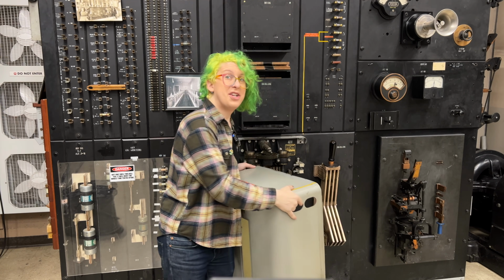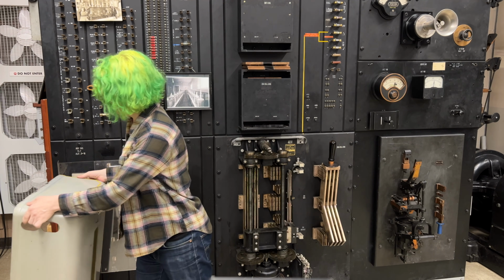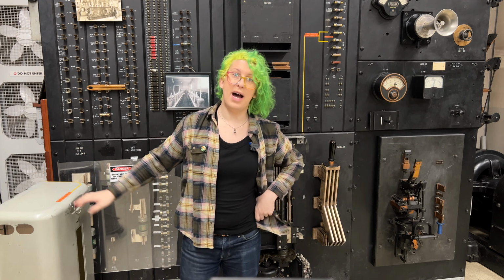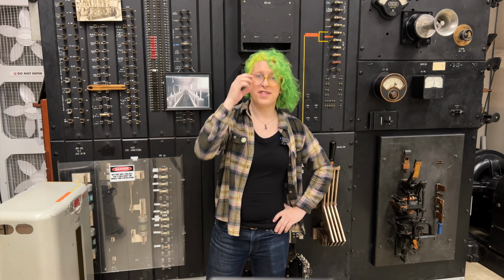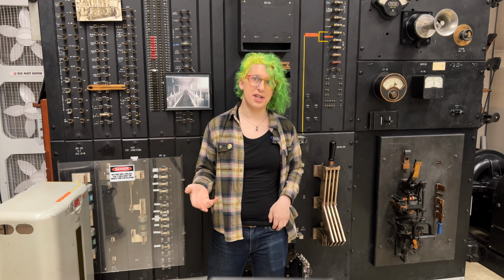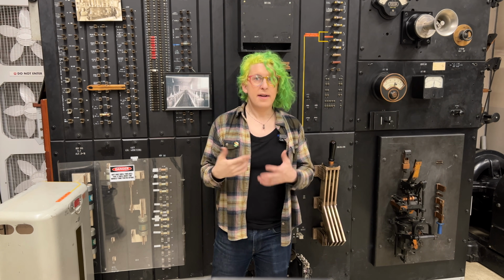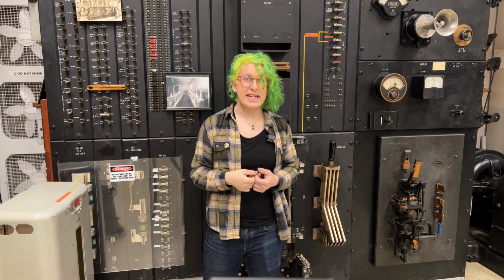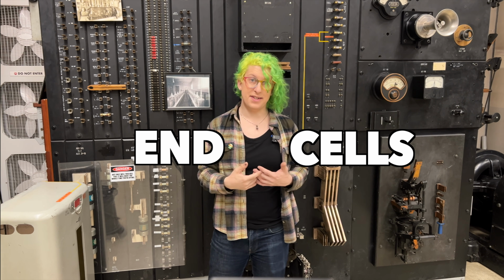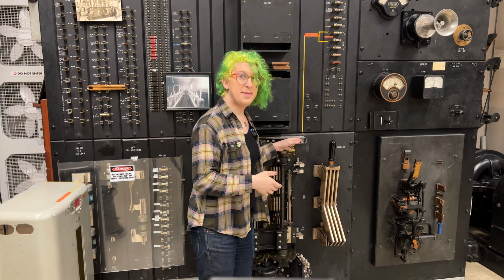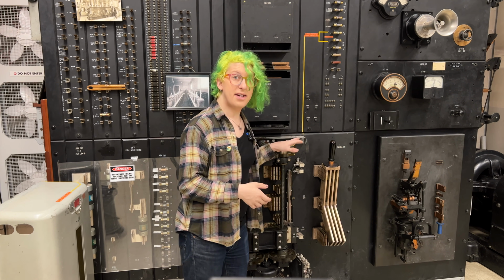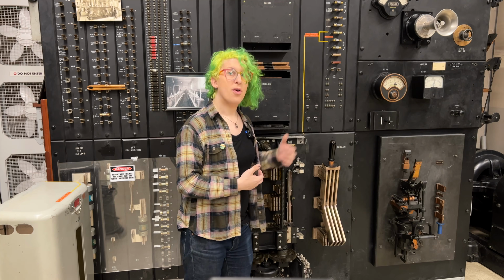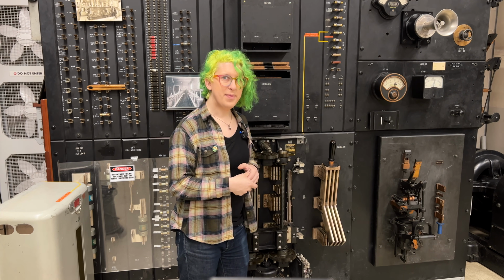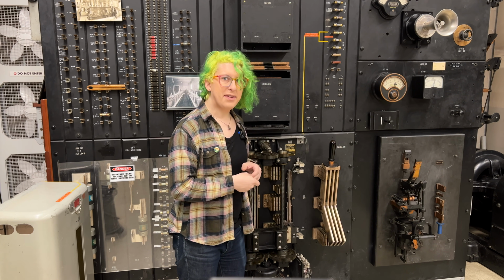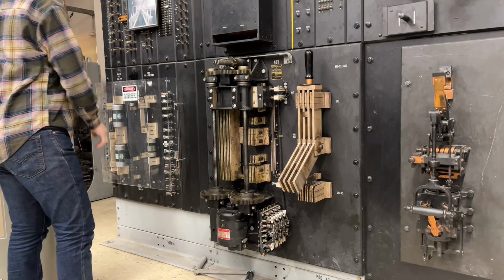Besides being constantly charged, the string of batteries that supplies the main 48-volt power usually has additional cells that can be cut into the charging circuit during emergencies. These cells are usually 2 volts each and are known as end cells. The large motorized switch in the center of the power board can be set to no end cells, 1 emergency group, or both emergency groups. It's normally operated automatically, but we can operate it here with these buttons as well.